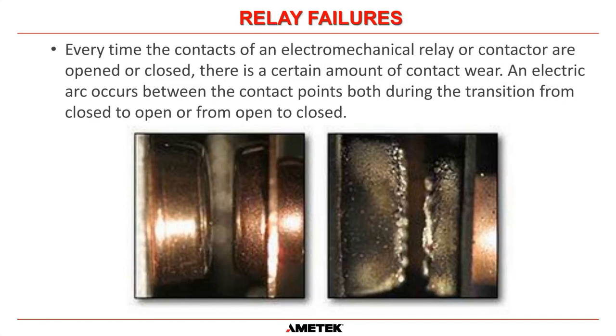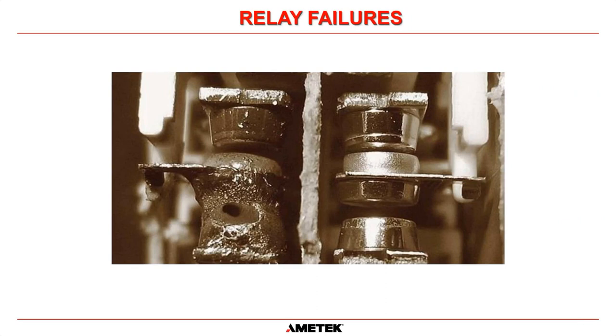And there's always going to be arcing whenever you go really close to closing or as soon as you open the contact. So you can see this is what the contacts look like when they are new. And after a few thousand operations, you can see that the arcing has caused degradation and oxidization on the contact surface of the relay. This will cause high resistance connections, which could cause faulty operation of the circuit that the relay is in. So it is very important, especially in relays that are critical to the operation of a piece of equipment, that they are replaced on a regular basis. So this never ever happens, because that is just asking for trouble if you left relays in long enough to have the contact surface area look like that. So that is why we always recommend replacing critical relays on an annual basis.